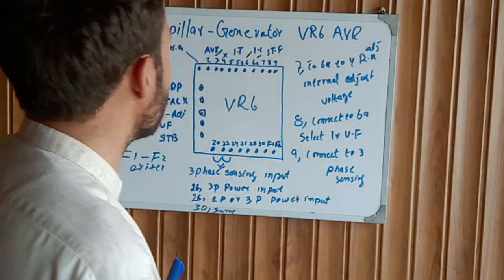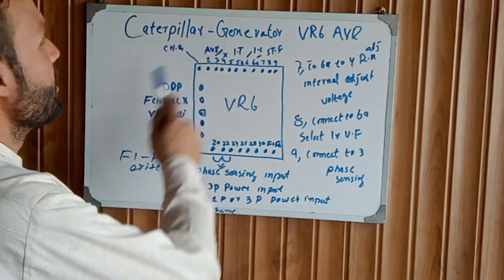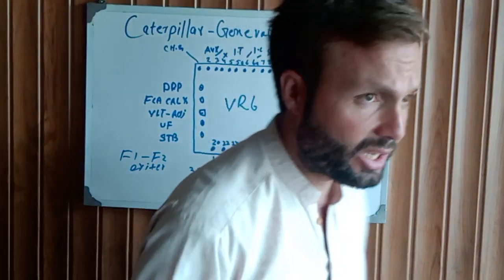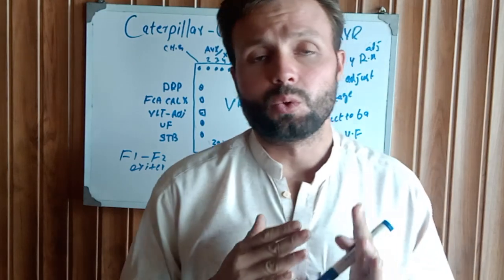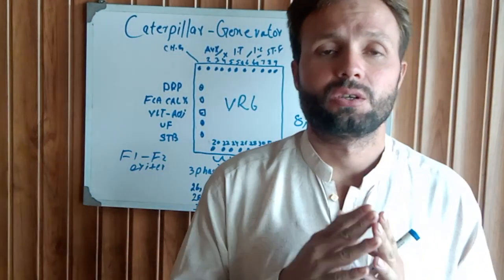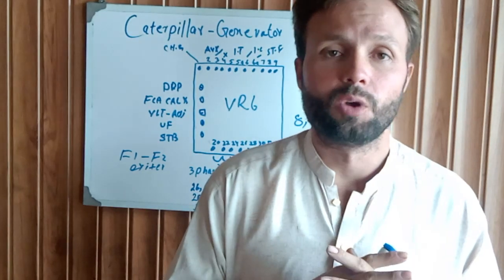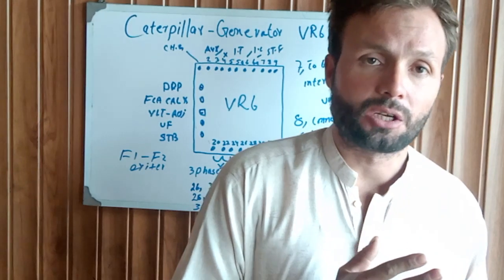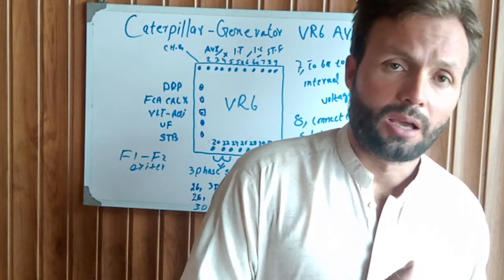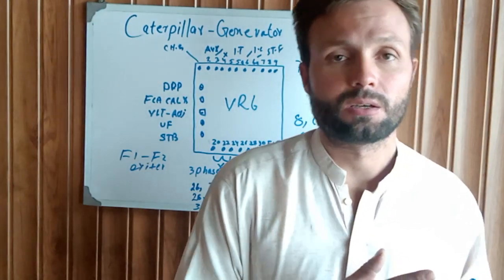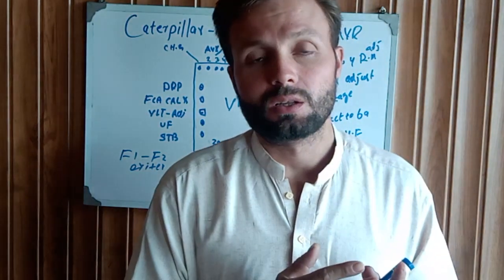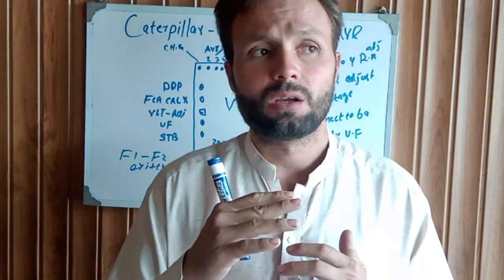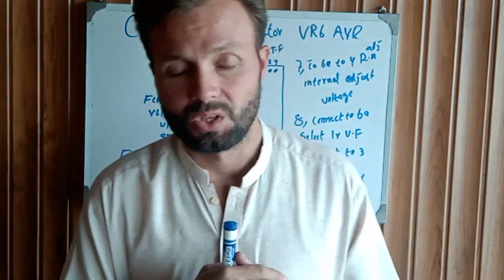Let me explain. I drew the diagram of Caterpillar Generator AVR VR6. Basically, the AVR works to adjust the generator voltage automatically. When the generator speed is increased, the AVR decreases the excitation system. When the generator speed is decreased, the AVR increases the excitation voltage to the excited system. This keeps the generator voltage stable.